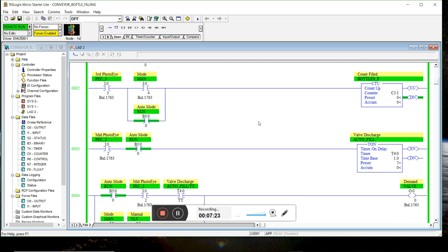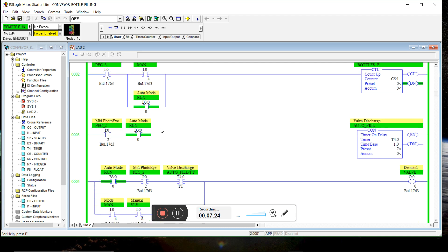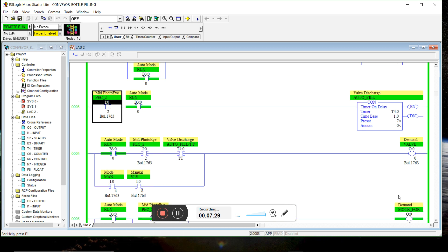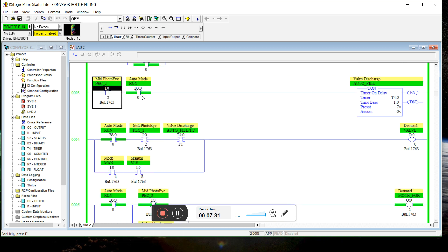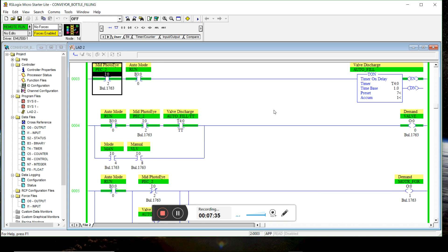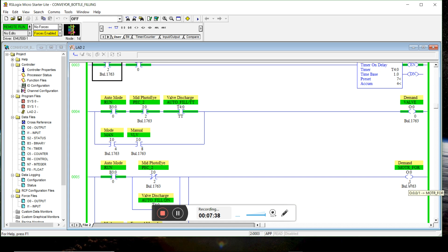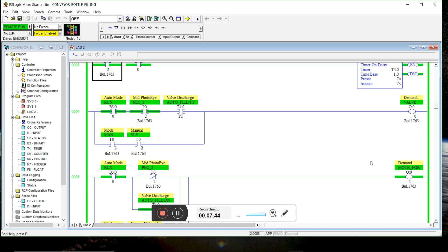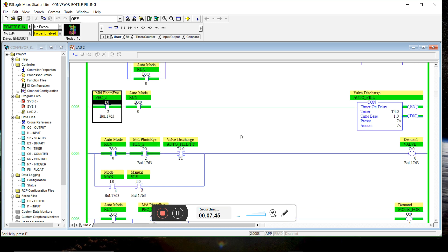And then it hits the middle photo eye. So let's see where we are right now. Motor's still moving forward. It hits the middle photo eye. We start counting. Motor stopped. Valve is discharging. Valve stops discharging after seven seconds and motor moves forward.